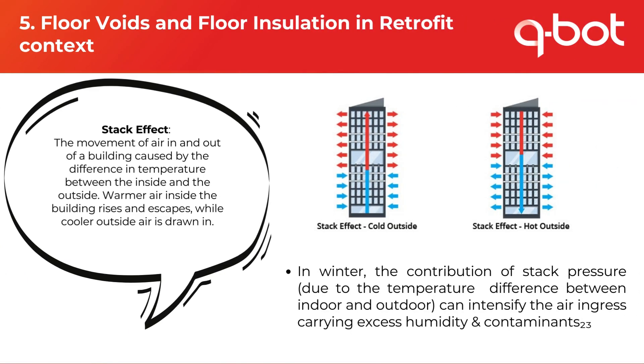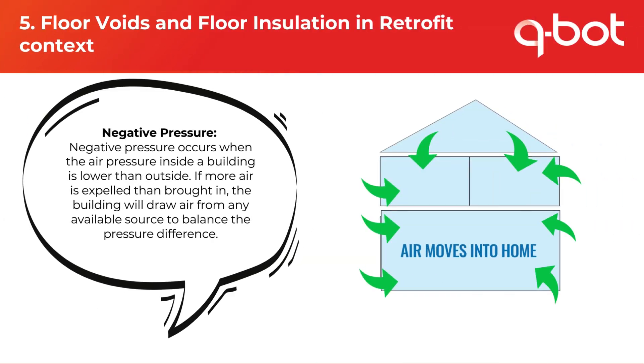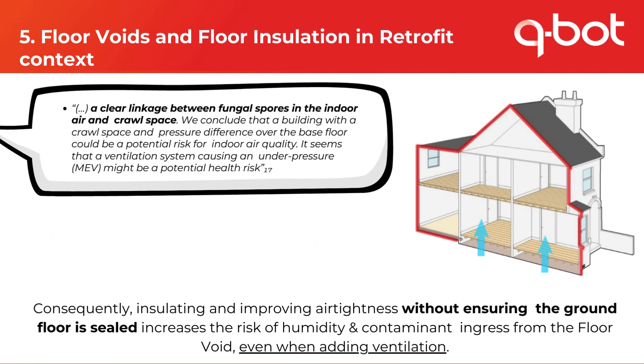This is due to a combination of the stack effect and negative pressure. Stack effect is the movement of air in and out of a building caused by the temperature difference between inside and outside — warmer air inside rises and escapes, whilst cooler air outside is drawn in. Negative pressure occurs when the air pressure inside a building is lower than outside. If more air is expelled than brought in, the building will draw air from any available source, most notably from the void. As a result, insulating and improving air tightness without sealing the ground floor increases the risk of humidity and contaminant ingress from the floor void, even when adding ventilation.